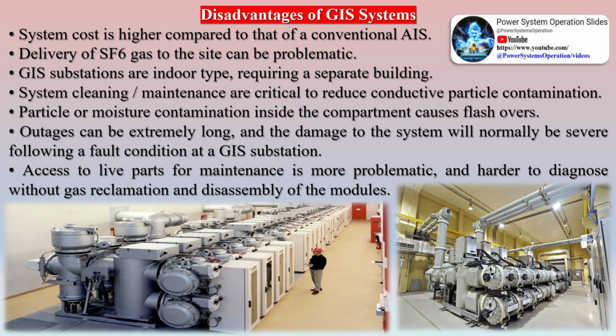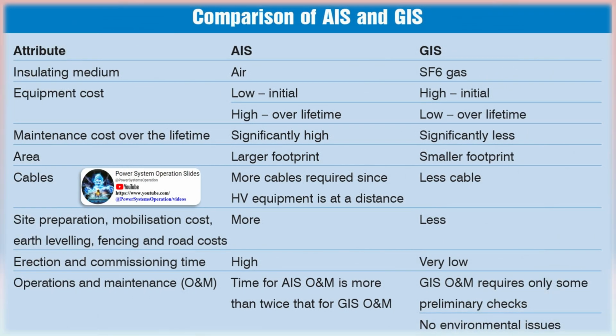Outages can be extremely long, and the damage to the system will normally be severe following a fault condition at a GIS substation. Access to live parts for maintenance is more problematic, and harder to diagnose without gas reclamation and disassembly of the modules.